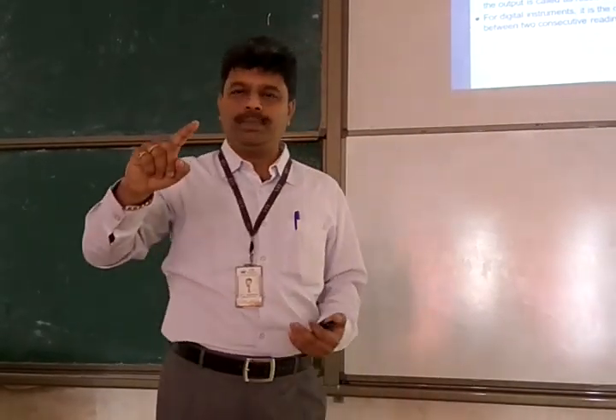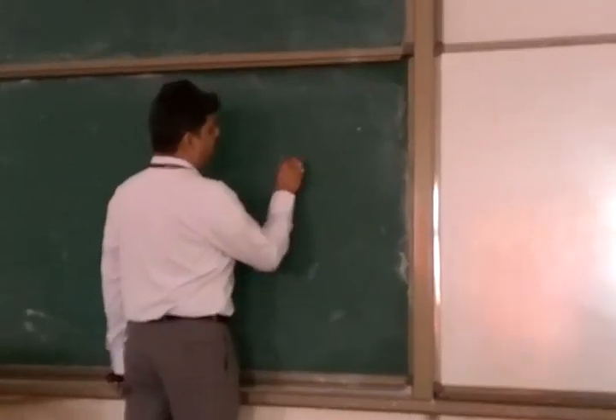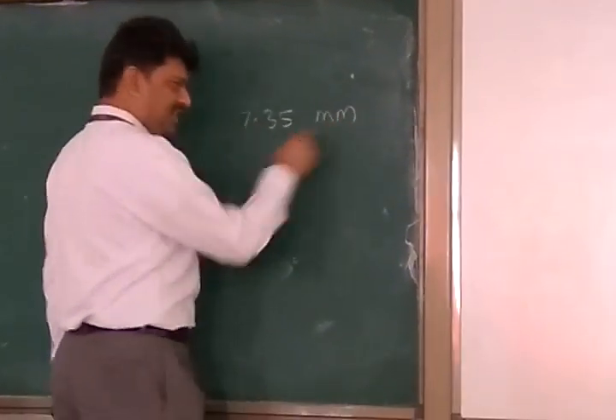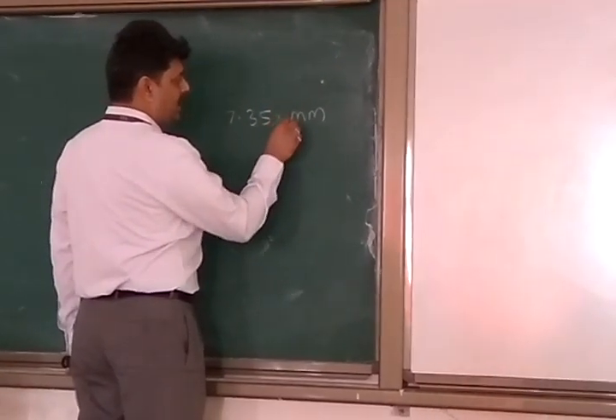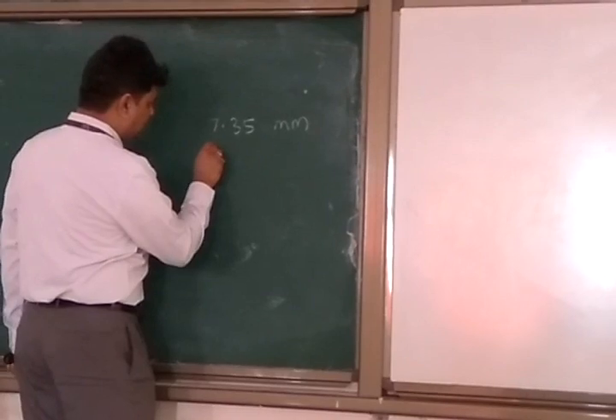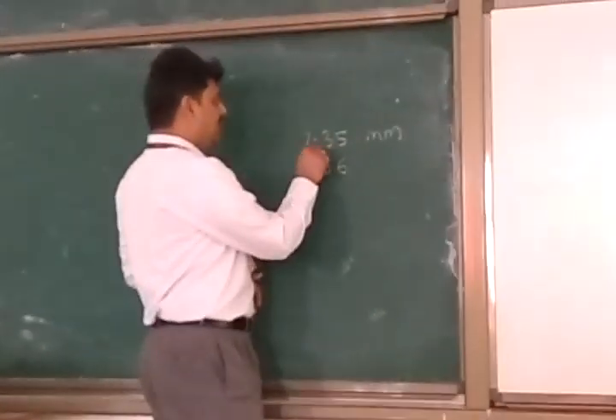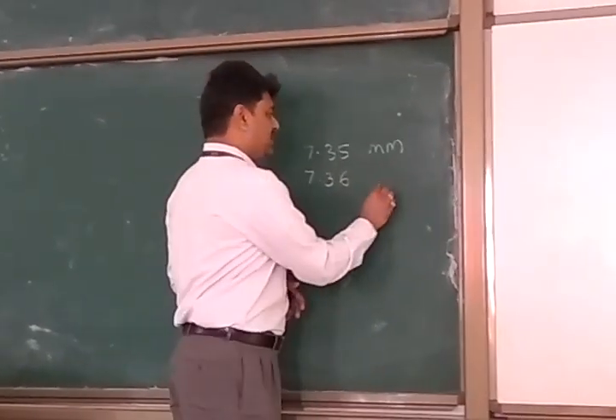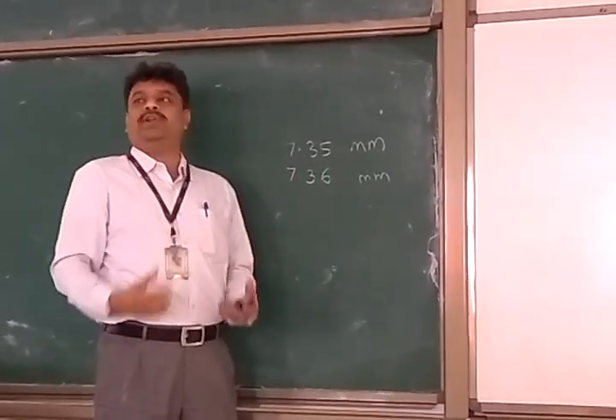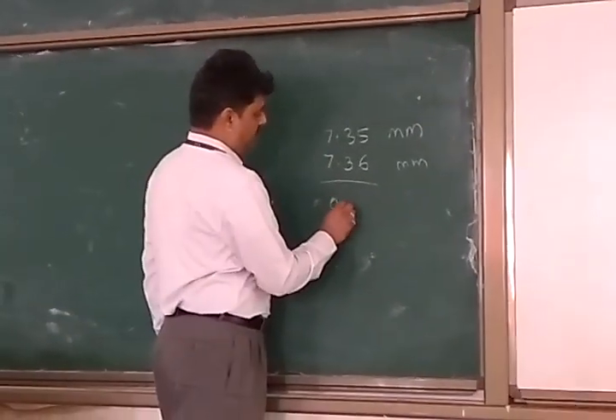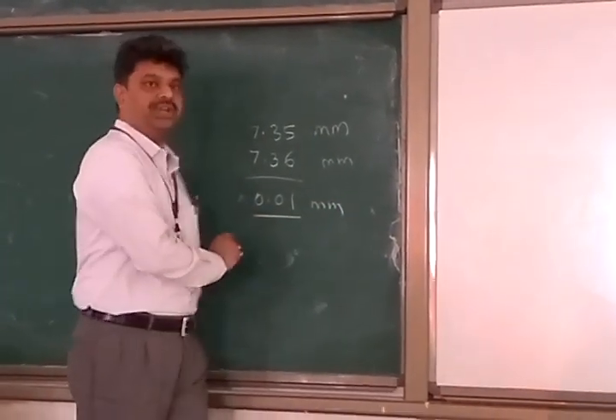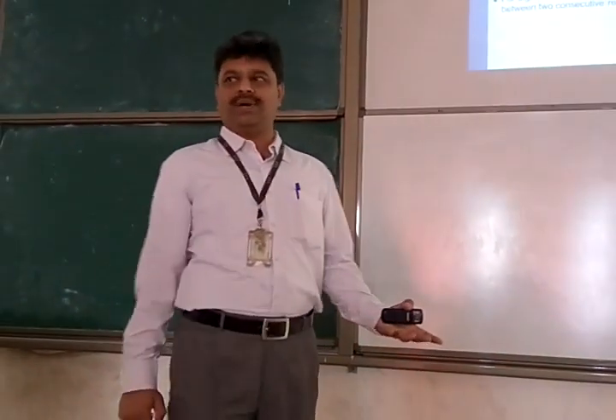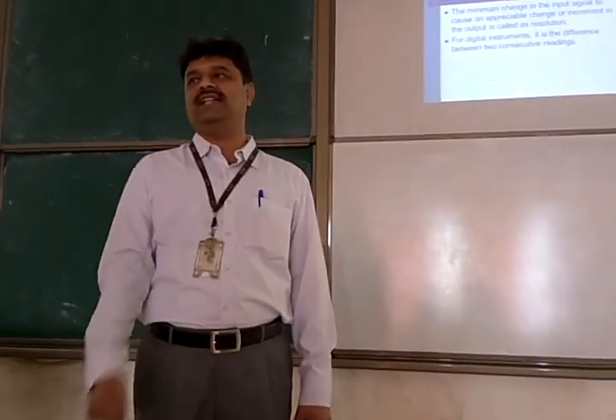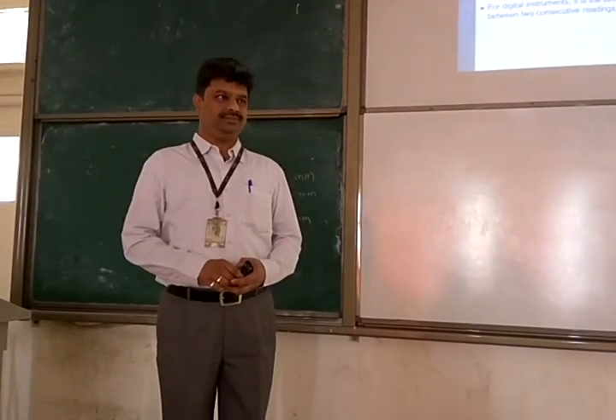If it is a digital instrument, to produce the next digit, what is the input signal required? For example, if it is a digital instrument measuring 7.35 mm, this digit at all you cannot measure further, only 2 digits you can measure. Resolution is the amount of signal required to make the next available reading. Next available reading after 7.35 is 7.36 mm. To make this, the amount of input signal I have to give is the resolution.